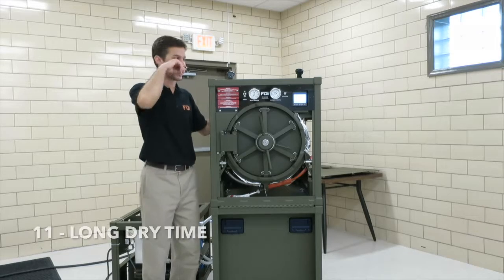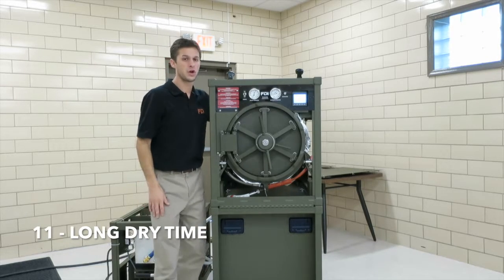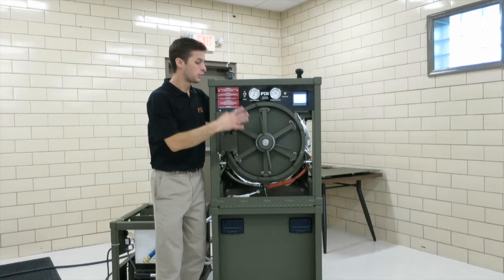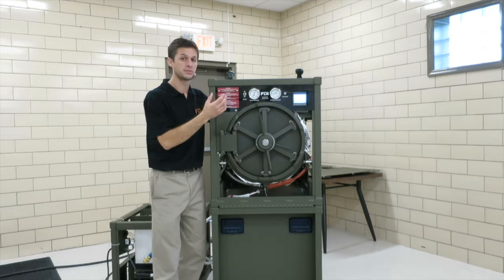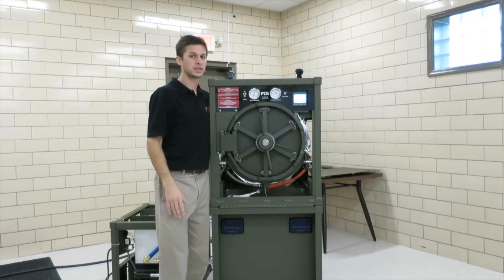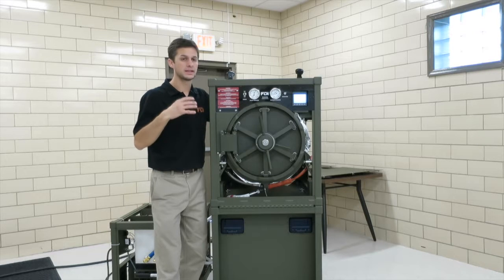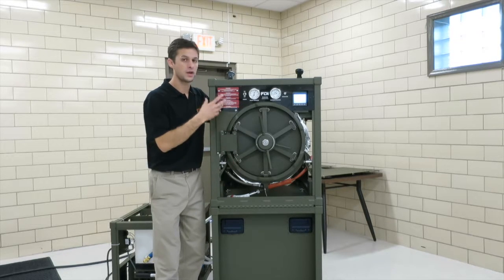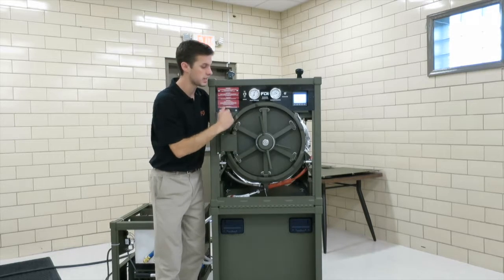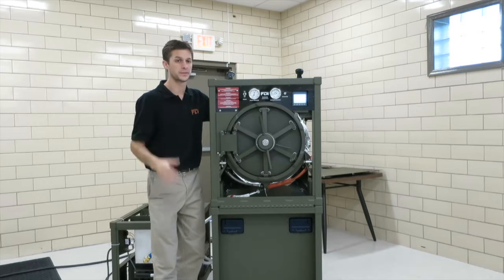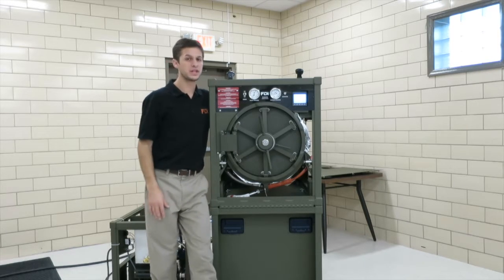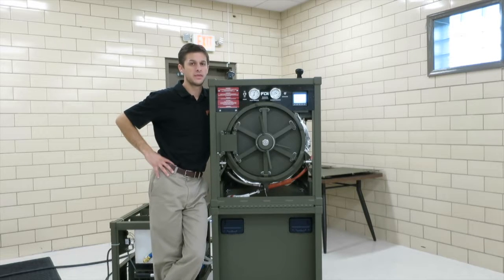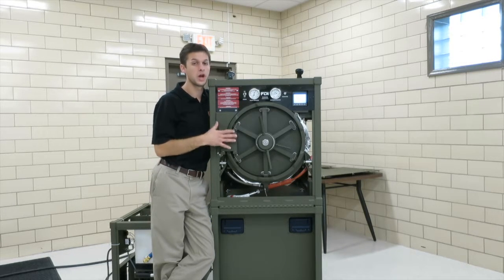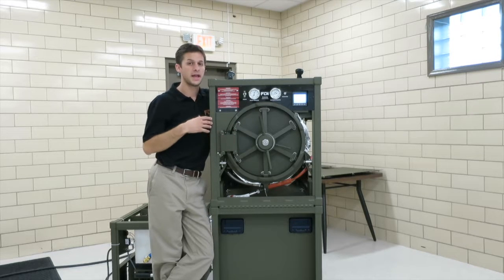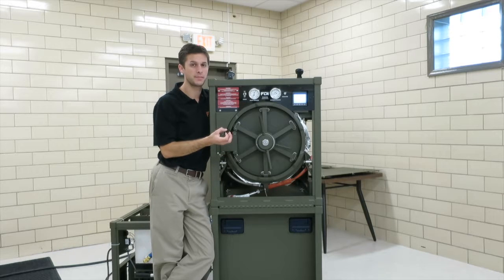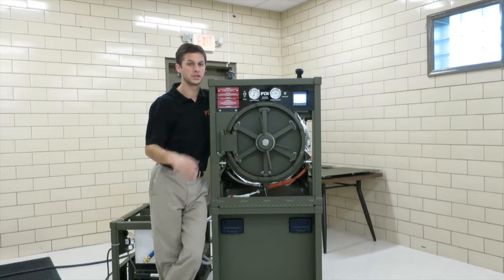Number 11 is long dry time. In order for things to dry, the water recovery system pulls a vacuum on the sterilizer, and there's a set point where it has to pull at least, say, 10 inches of mercury. That allows all that condensation to flash off. So when there's a vacuum, it allows the contents inside the chamber to dry. If you didn't have a deep enough vacuum, then that watchdog timer would know that you're really not drying sufficiently. And if you don't hit that set point of vacuum for a long enough period of time, you'll get this long dry time, number 11.